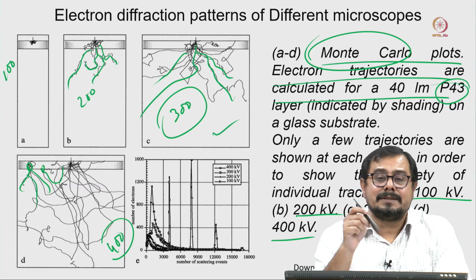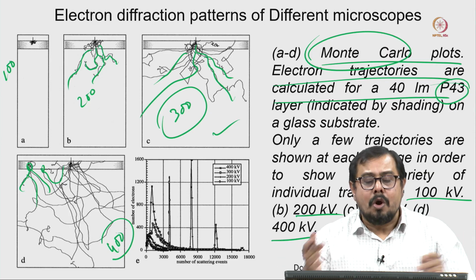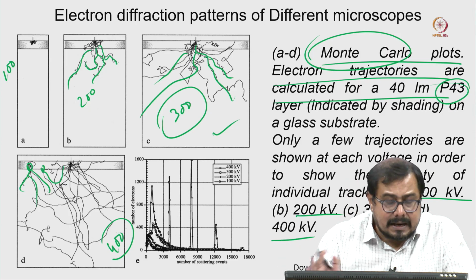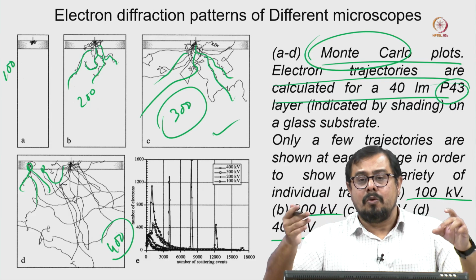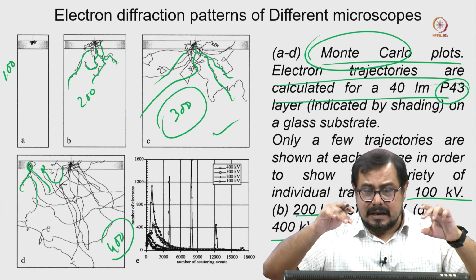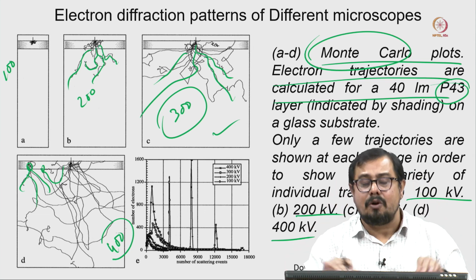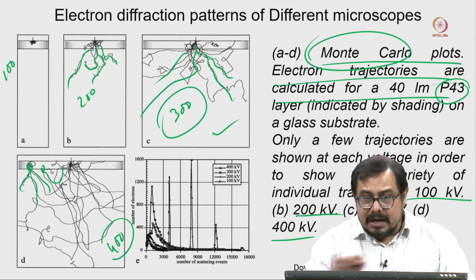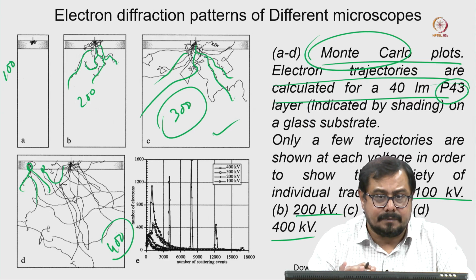That is the reason fast readout is very important, which is not possible when we are using the CCD camera. It is only possible if we directly collect the electron and record it, hitting the scintillator and then recording that signal immediately. Then the readout will be fast and we can correct any kind of motion.